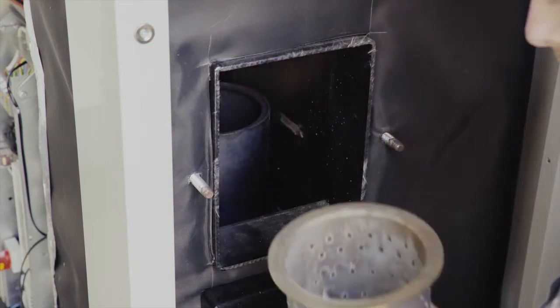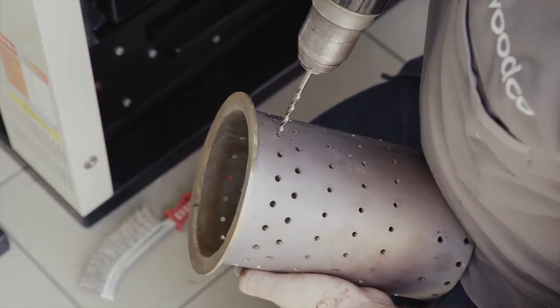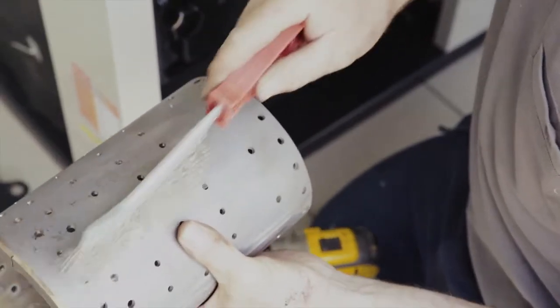Ensure that all the air holes in the burner pot are clear. This is done by drilling with a 5.5 millimeter bit through the big holes to remove any carbon. Use a 4 millimeter bit for the smaller holes.